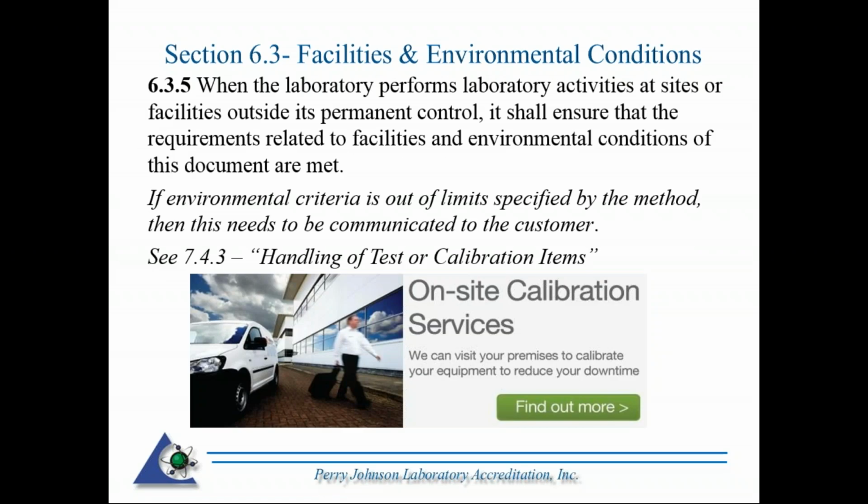When the laboratory performs laboratory activities at sites or facilities outside its permanent control, it shall ensure that the requirements related to facilities and environmental conditions of this document are met. So hence, on that example I provided previously with temperature controlled at 68 degrees plus or minus 2 degrees Fahrenheit, relative humidity less than 50%.